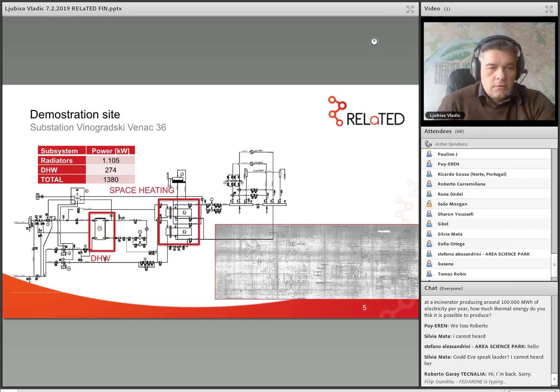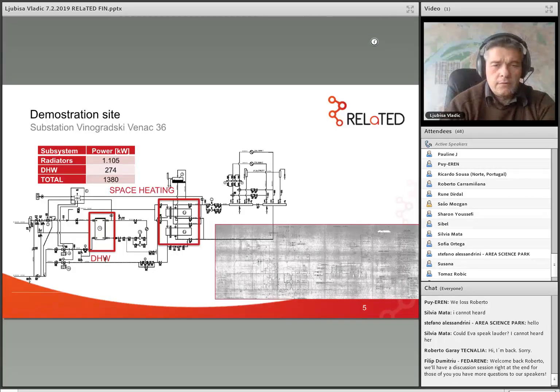This is a technical scheme of substations for space heating and domestic hot water - this is our typical concept of this type of substation. In most cases we have new heat plate exchangers for space heating, but in this one we have plate heat exchangers for domestic hot water and 2 old type tube heat exchangers for space heating. Power of this substation is more than 1 megawatt, and we have radiators and domestic hot water, as I mentioned.